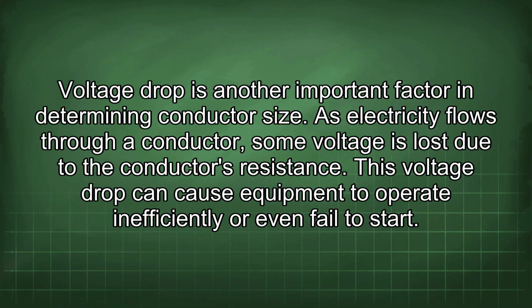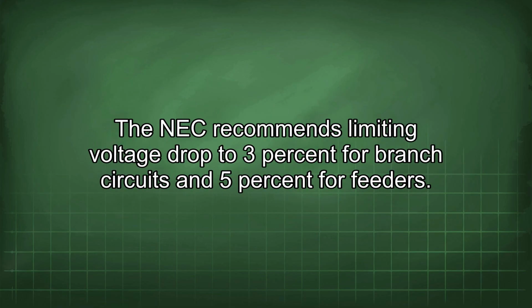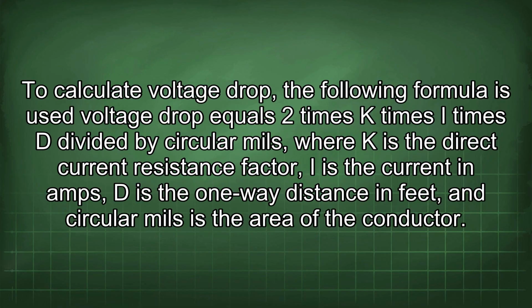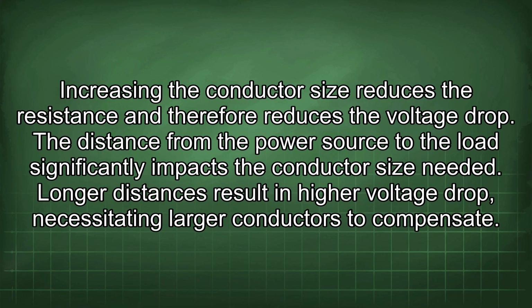Voltage drop is another important factor in determining conductor size. As electricity flows through a conductor, some voltage is lost due to the conductor's resistance. This voltage drop can cause equipment to operate inefficiently or even fail to start. The NEC recommends limiting voltage drop to 3% for branch circuits and 5% for feeders. To calculate voltage drop, the following formula is used: voltage drop equals 2 times K times I times D divided by circular mils, where K is the direct current resistance factor, I is the current in amps, D is the one-way distance in feet, and circular mils is the area of the conductor. Increasing the conductor size reduces the resistance and therefore reduces the voltage drop.